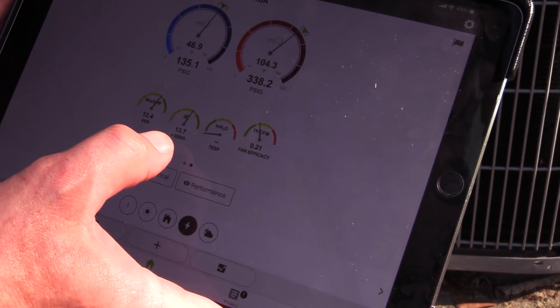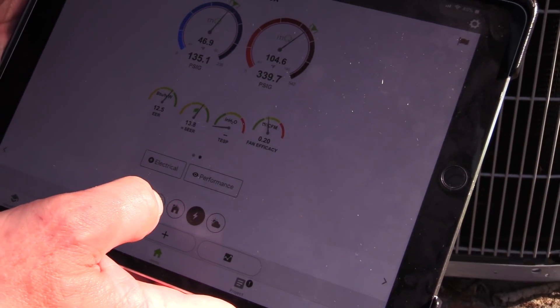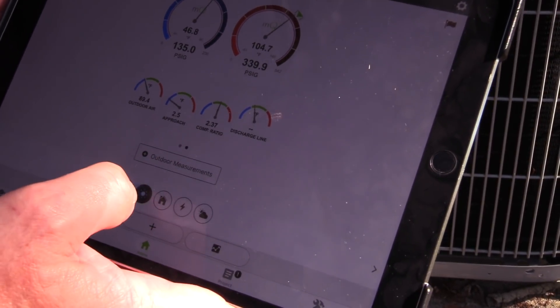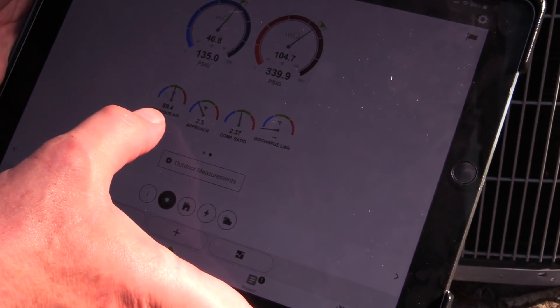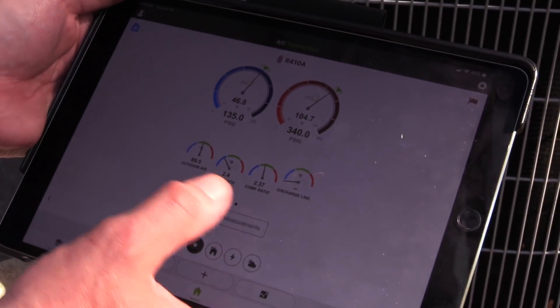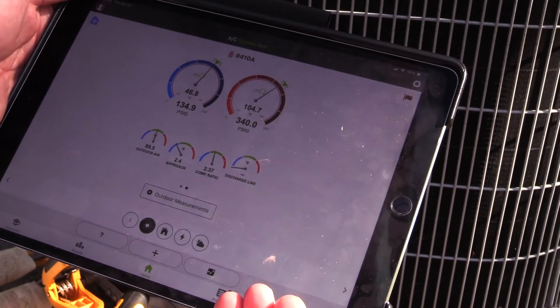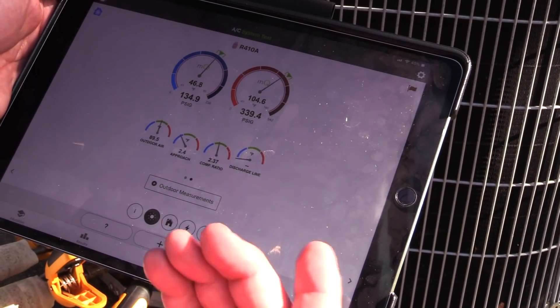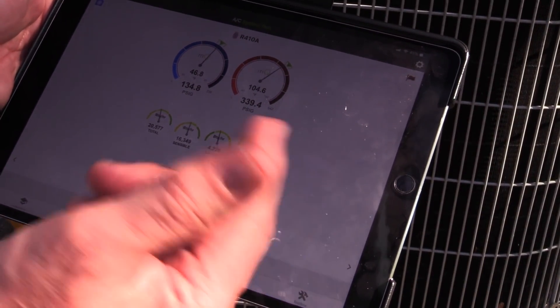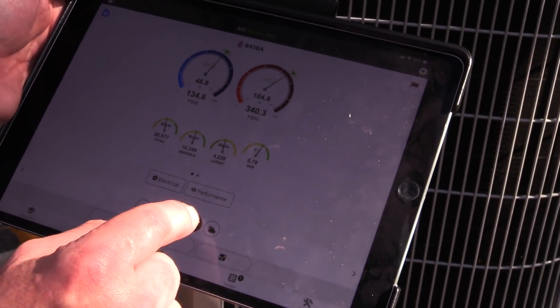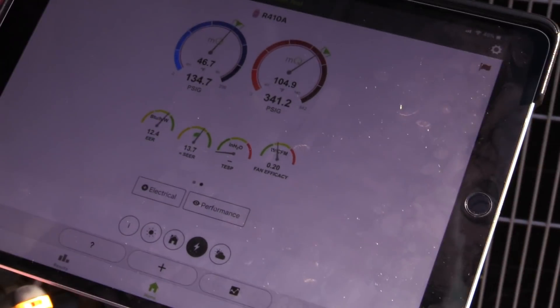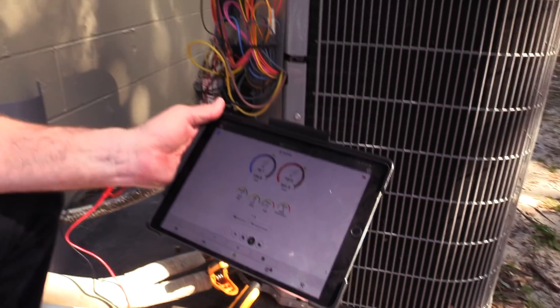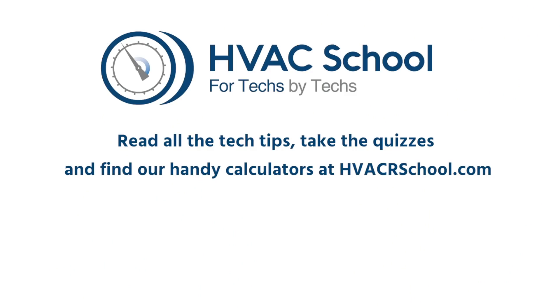Let's see if we can get our outdoor air temp—we're at 90 degrees versus 95. So with the higher head pressure at design conditions, we would see a higher amp draw and it would push it down more towards the 13 SEER range. But this is all looking really good right now and we're good to go. Any questions on that, Brian? No, that's it. Yeah, pretty cool. All right, very good, thanks.